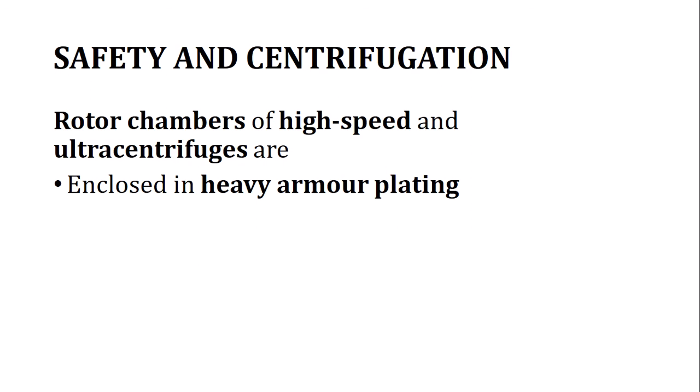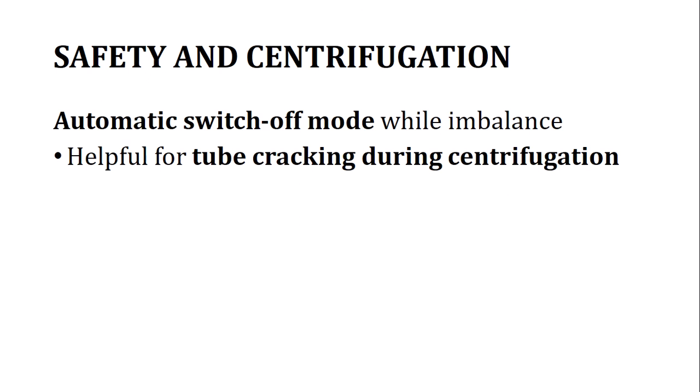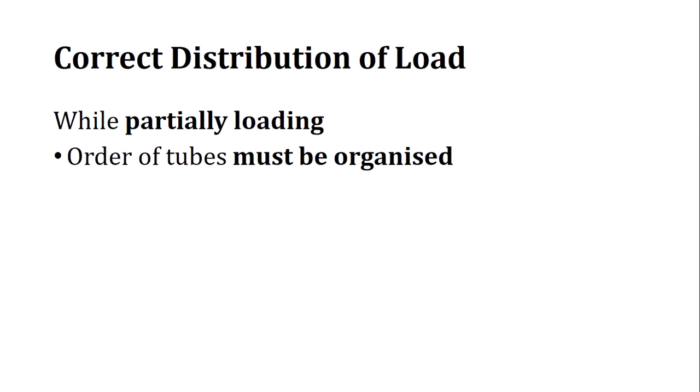For safety: rotor chambers of high speed and ultracentrifuges are enclosed in heavy armor plating to prevent damage in case of mishap. Automatic switch-off mode during imbalance is helpful for tube cracking and buffer drainage. Correct distribution of load is very important — tubes must be organized in counterbalancing pairs. For example, 3 ml, 5 ml, and 10 ml tubes should each be counterbalanced with tubes of equal volume.